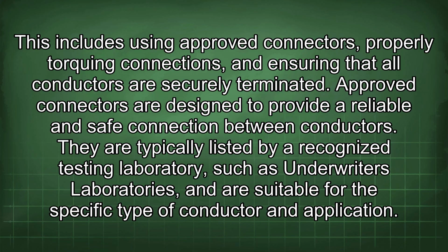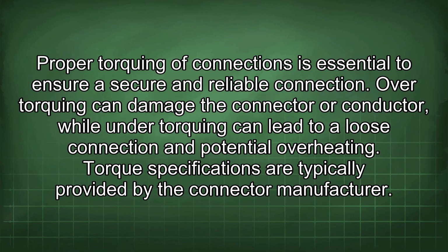Approved connectors are designed to provide a reliable and safe connection between conductors. They are typically listed by a recognized testing laboratory, such as Underwriters Laboratories, and are suitable for the specific type of conductor and application. Proper torquing of connections is essential to ensure a secure and reliable connection. Over-torquing can damage the connector or conductor, while under-torquing can lead to a loose connection and potential overheating. Torque specifications are typically provided by the connector manufacturer.